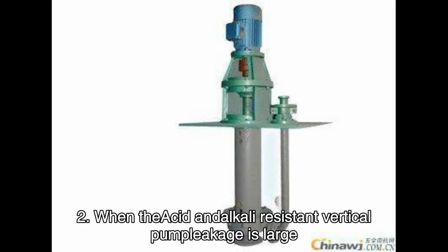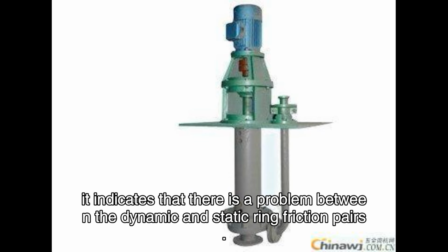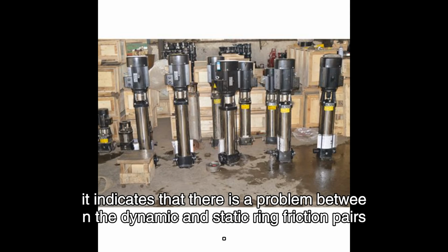2. When acid and alkali-resistant vertical pump leakage is large, it indicates that there is a problem between the dynamic and static ring friction pairs.